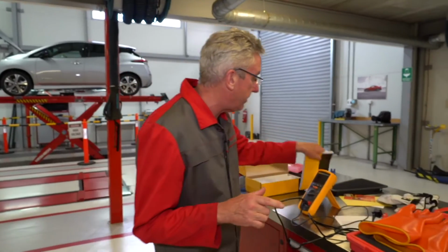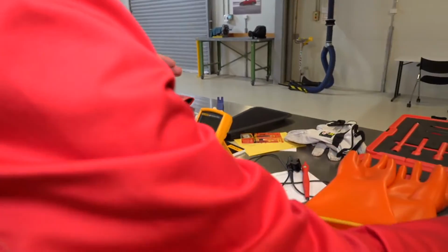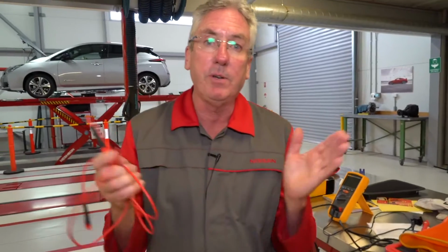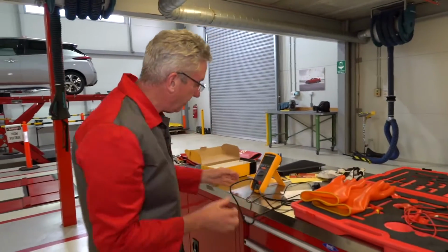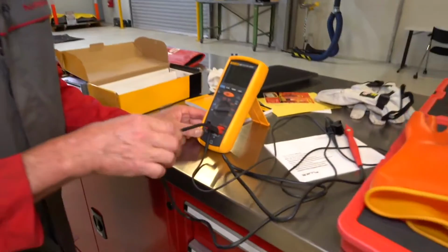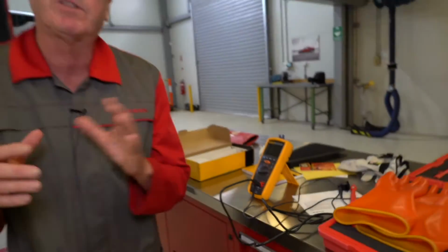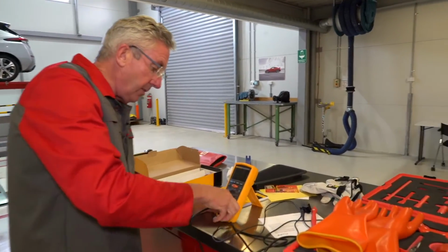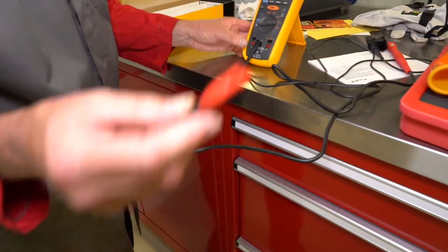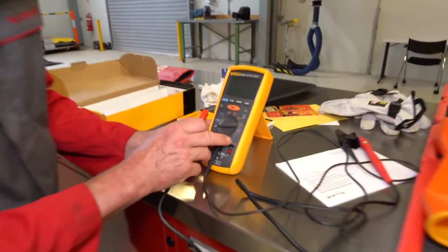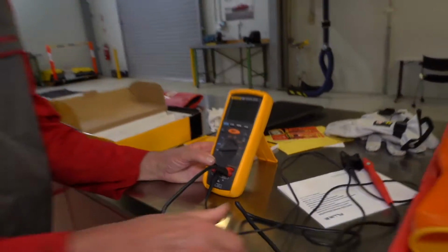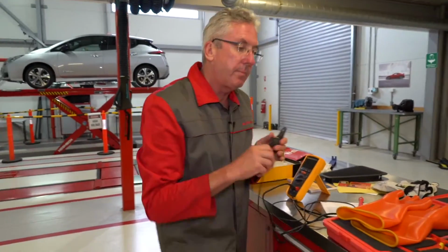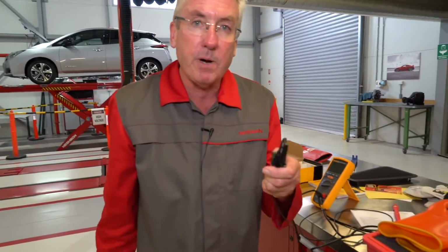Now, talking about the insulation resistance tester, here it is. I've taken out my usual red lead that I would use to do voltage, I don't need it, and I've replaced it with this thick one here. Have a look here. And remember, this insulation resistance tester is rated to 1,000 volts. We're only going to put 500 in because in this test, that is what the ESM asks for. So, this is a special triangular connection, and I'm going into this port here, which is voltage and insulation. I still have my COM lead in, my black lead, but I've taken my pointy probe off and I've put my crocodile clip on.